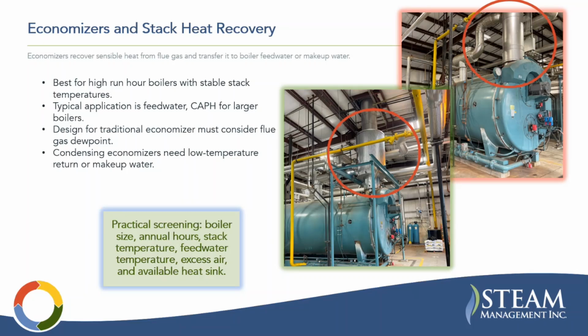Some rules of thumb: a 1% efficiency increase per 11 degrees of feed water temperature increase. An economizer that recovers 5% of boiler input should easily have a 2-year payback in a year-round application. So you're going to have very good paybacks if the conditions are right. And then for combustion air preheaters, there's a 0.5% efficiency increase per 20 degrees of combustion air temperature increase.